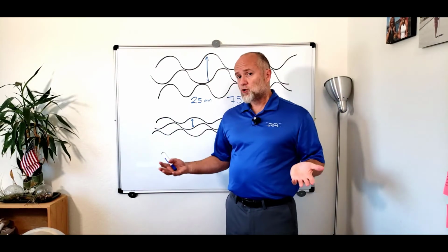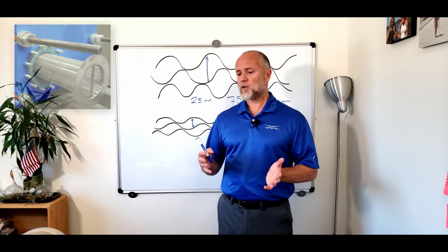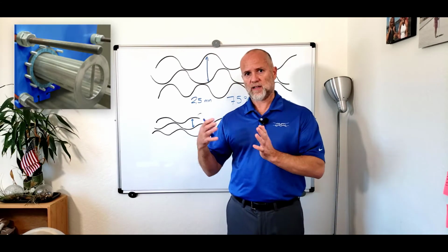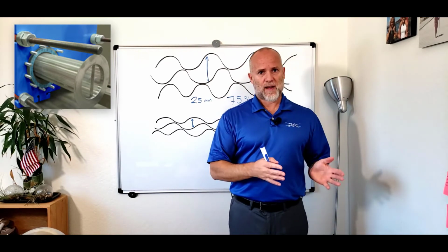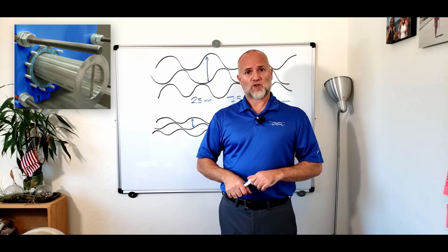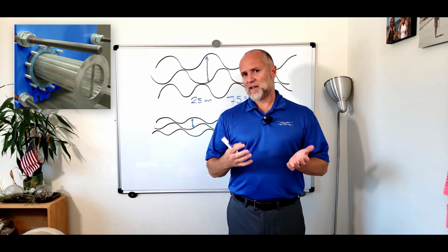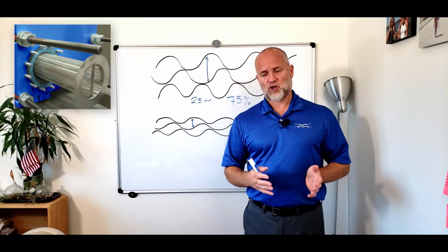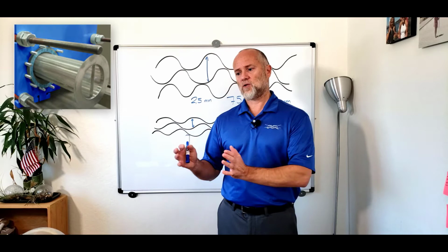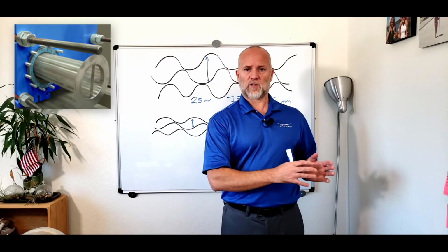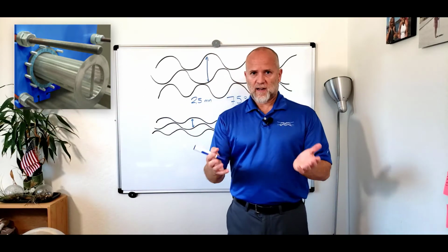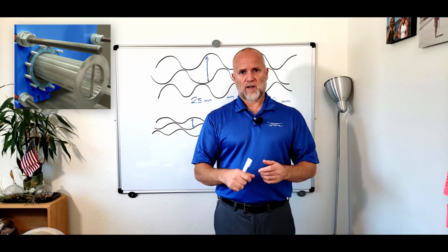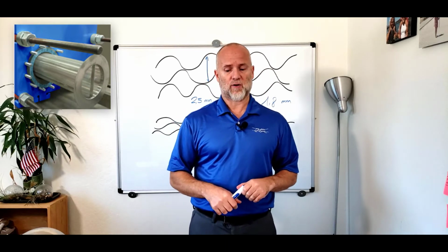And the third solution, of course, is the port filter. The port filter comes with the heat exchanger, so it's provided by the vendor, so you don't have to worry about matching the mesh with the size of your channels, because that is done by the vendor. And it has another advantage: it is inside of the heat exchanger, and you want to position your strainer as close as possible to the heat exchanger so you don't have any contaminants after the strainer. Here you can see a picture of a port filter, which is embedded inside of the heat exchanger.